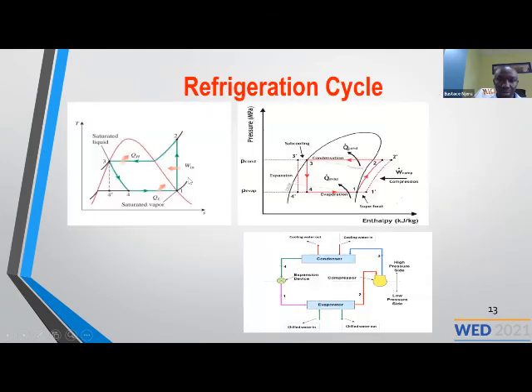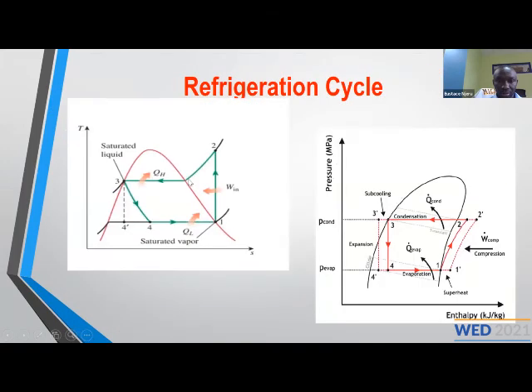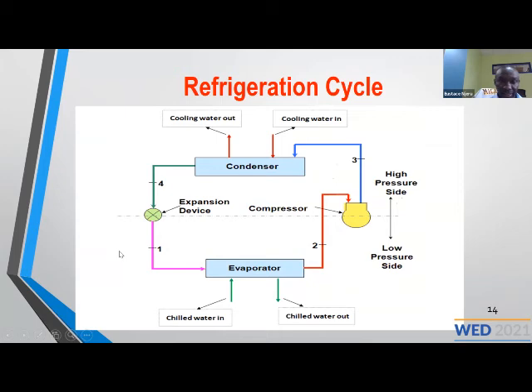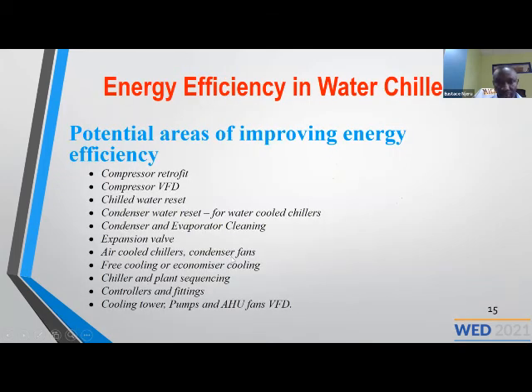In such systems, for the air-cooled chillers, you need to accompany it with a system which is incorporated to control the fans, based on the temperature of the chilled water. If you don't require a lot of chilled water, you need to accompany it with chilled water reset. When you do the chilled water reset and you find that you don't require water at very, very low temperatures, you also need to reduce the number of fans which are running or the speeds of the fans. And there you can save some energy.